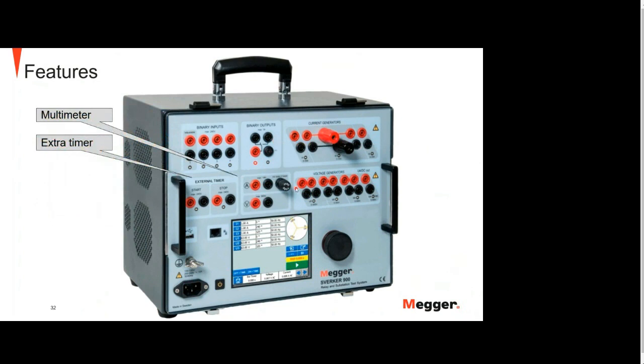We have a multimeter. Everybody who knows the Sverker one-phase testers, Sverker 750 and 780, we have the same multimeter there: ammeter, voltmeter, and they could calculate between each other impedance or cos phi, also phase angles between these 2 inputs. We have an extra timer, which could measure an extra time, for example, on the auxiliary contact. This is the start input and this is the stop input for that timer, and it's always accessible here. The current and voltage are always accessible at the bottom of the screen, and you can see impedance and other measurements calculated from these 2 if you push on these arrows.